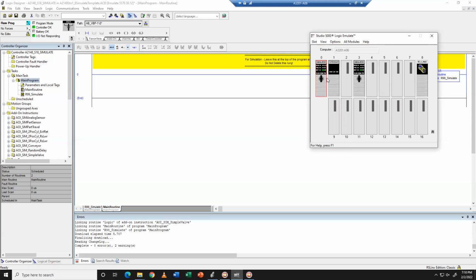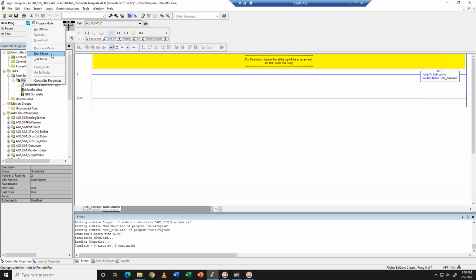On some of the newer controllers, it's not a key switch but a tiny physical switch. If it's in program, you cannot put the processor into run. If the key switch or switch is in the middle position, it typically points to a remote mode - called remote service, remote program, or program access depending on the manufacturer - meaning you can get online with the processor and program it. So in the middle position, you can actually force it into program mode or into run mode.